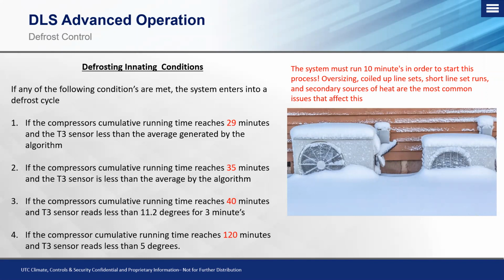And then of course our secondary heat sources are the most common issues that affect that unit running 10-minute minimum to start looking at the initiating conditions. Now here's the issue. The system can run 9 minutes on the first call, 8 minutes on the second call, 9 minutes on the third call. Okay, so you've had 3 calls for heat. Neither one of them have reached 10 minutes, and neither one of them have had a defrost cycle. So through those 3 cycles, we now have excess frost that's starting to build up on the coil. Okay, and this usually happens because something was either oversized and it's short cycling, or we had a secondary heat source that's taking runtime away from the compressor.